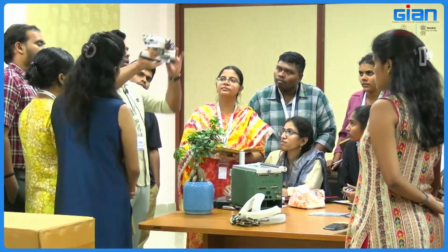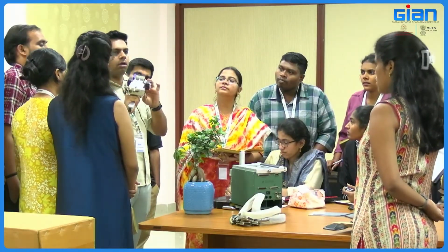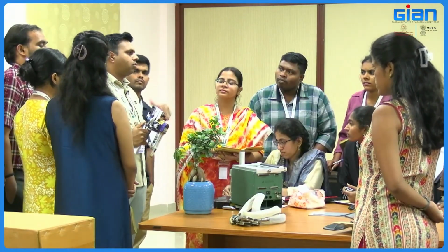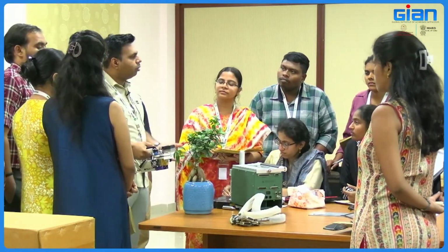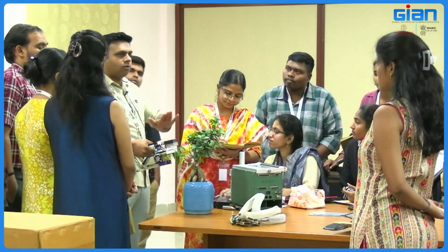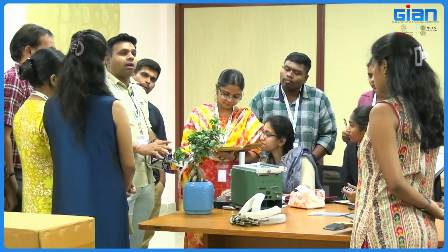Okay, so once it is tight, you can go to any light source and see whether there is light leakage or not. It should not be too tight. If it is too tight, then you will damage the leaves. Okay, and it should not be loose. If it is loose, then CO2 will escape. Your reference CO2, whatever you are maintaining, will escape. Got it? And there is also a light detector.